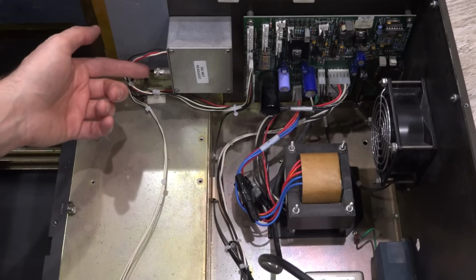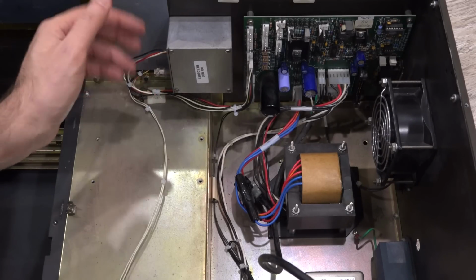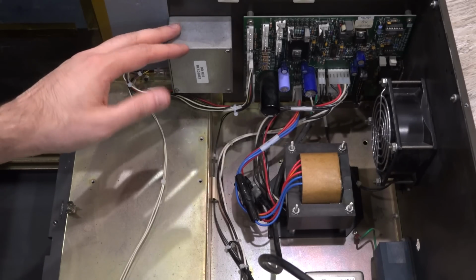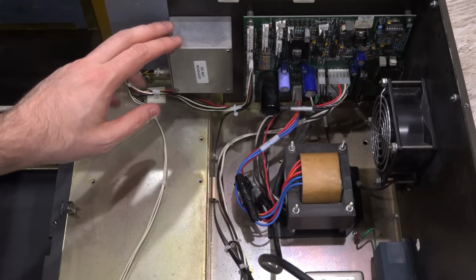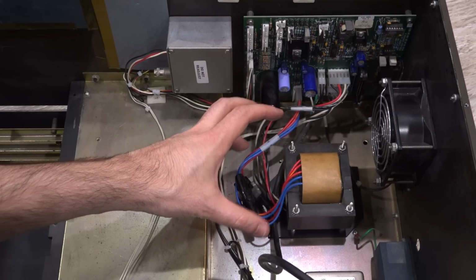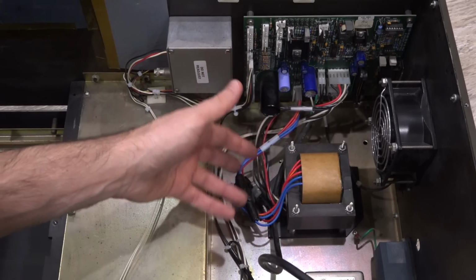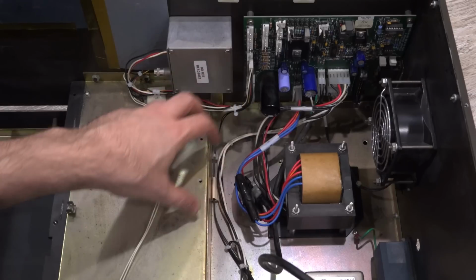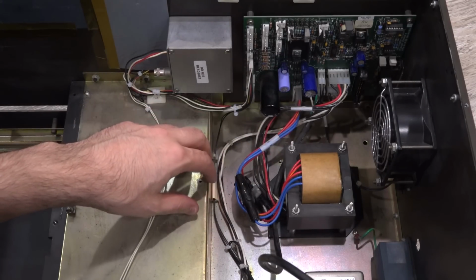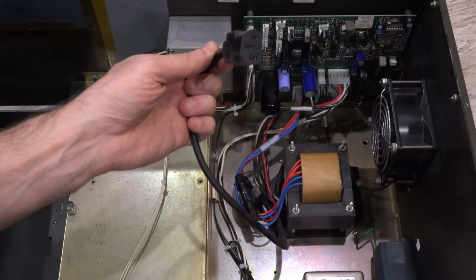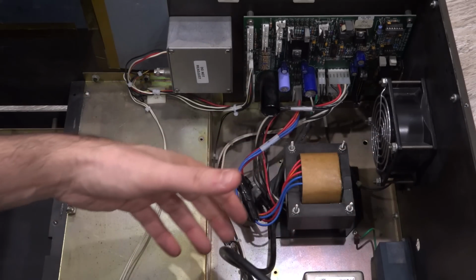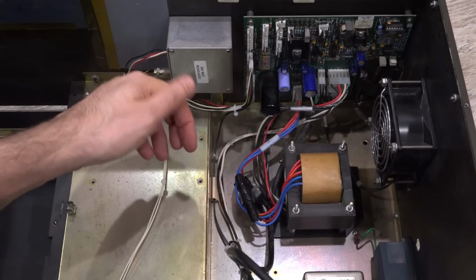This over here does have a high voltage BNC connector, so it could be the focusing voltage generator segment for the X-ray tube itself. There's a transformer here for the main input, and it is only 115 volt because it's directly linearly connected, so there's no switching supply in any of this. And there's nothing unusual. There's a power cable here. This was going into the X-ray high voltage power supply, which was sitting over here, so that's gone right now, so I can clean it up.